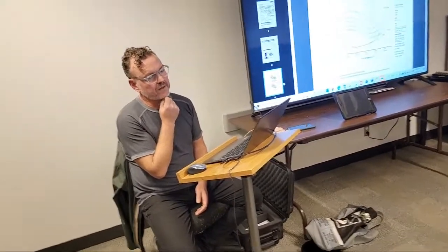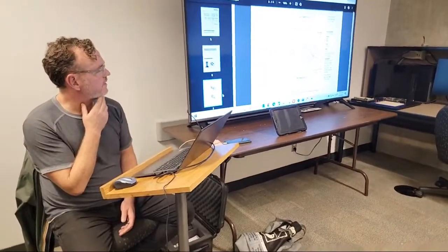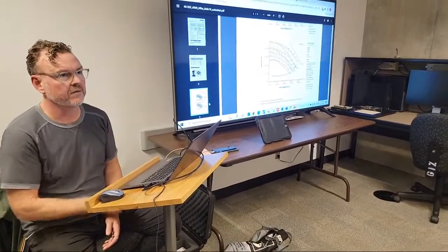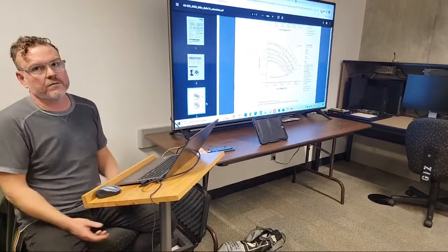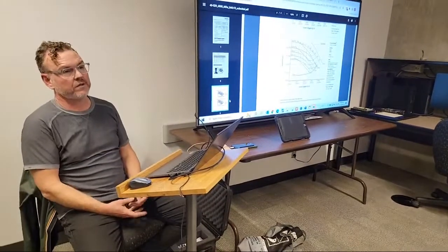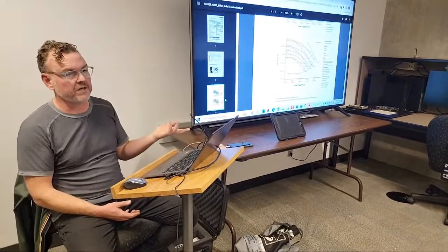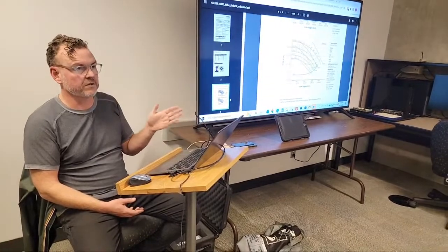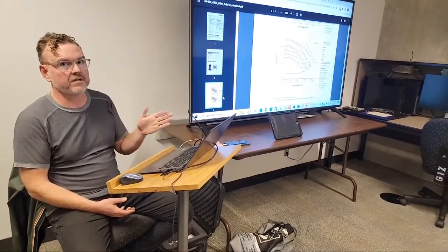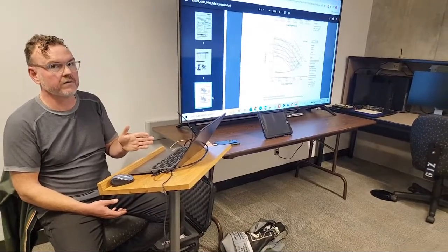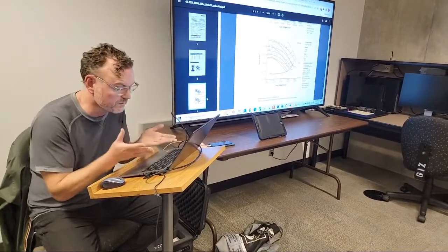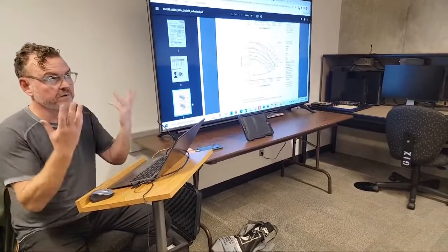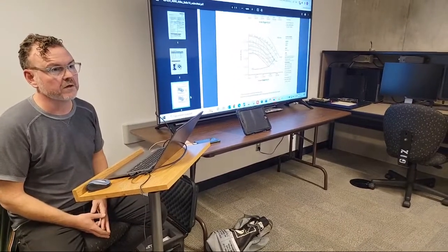Well, interesting that you're saying that. One of the things is, I can't do anything without the pump curves. You walk into a mechanical room and they're saying, well, you have an issue. And I say, okay, I need the submittal data. I need the design documents to know what I was supposed to be at. Then I need the commissioning documents to know where we ended up. And then I need to be able to visually observe the pressure gauges in the room, if I don't have that information already pulled up into the cloud in building automation, right?